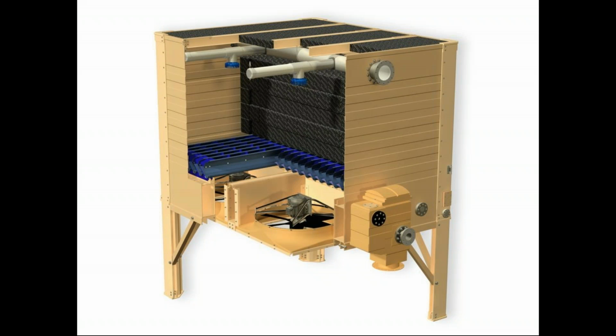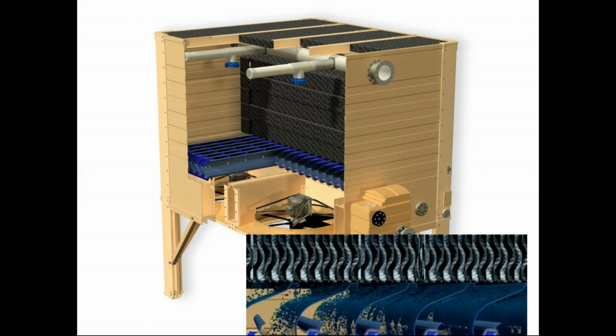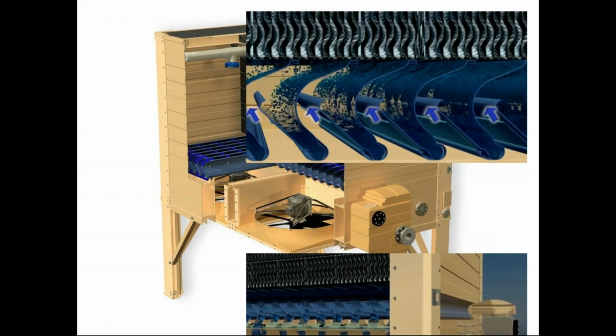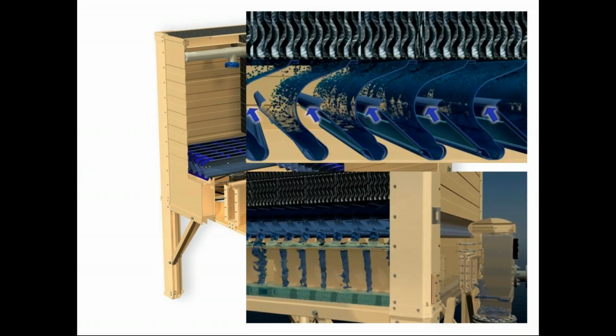I'm going to work the water side of it first. So the water will go into the inlet on the upper and middle part of the tower, and it'll flow through the variable flow nozzles, which are shown in blue here. Those variable flow nozzles vary the flow down to a third of the design flow. It's really the only variable flow nozzle. Then the water goes through the fill, and then it goes into our water collection system, and then it flows into the high velocity basin.